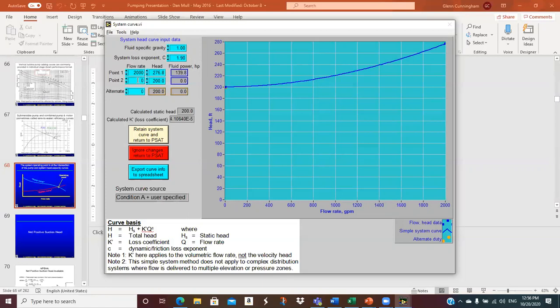So it's common. You don't have to. You can put in any 2 points that you know on the system curve, and it will fit it. But it's very common to use the zero flow point. If it's a closed loop, it's 0, 0, because a closed loop has no static head. Well, that's pretty darn easy.